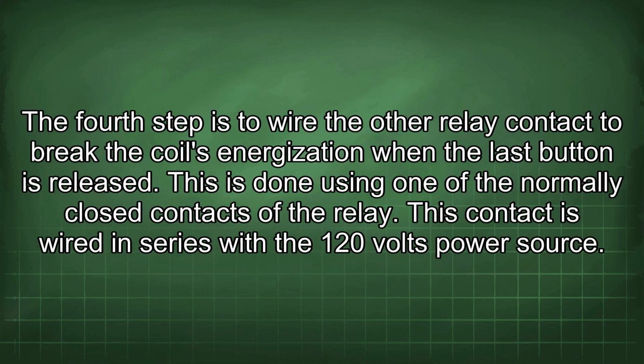The fourth step is to wire the other relay contact to break the coil's energization when the last button is released. This is done using one of the normally closed contacts of the relay. This contact is wired in series with the 120 volts power source.